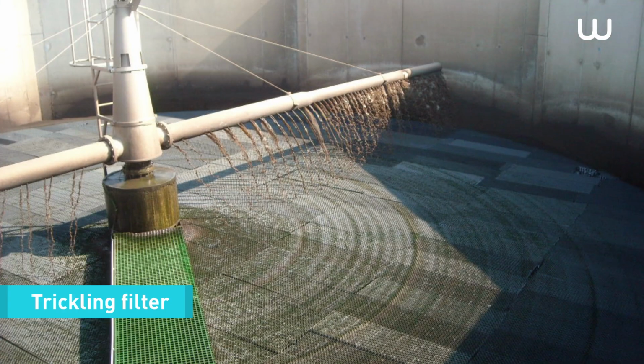Lastly, it is important to note that the distribution of consumption depends on the technology used and on the type of plant. Indeed, in plants using bacterial beds, the item that consumes the most energy linked to aeration is not present, thereby making the plant less energy intensive. So in regards to this technology, the energy distribution therefore varies greatly from one plant to another.